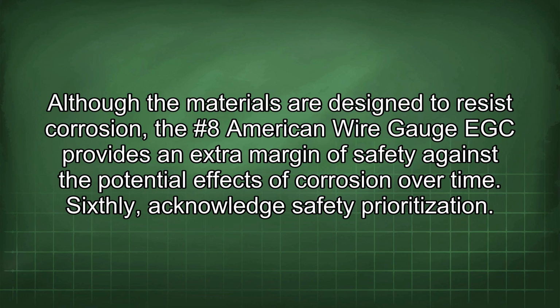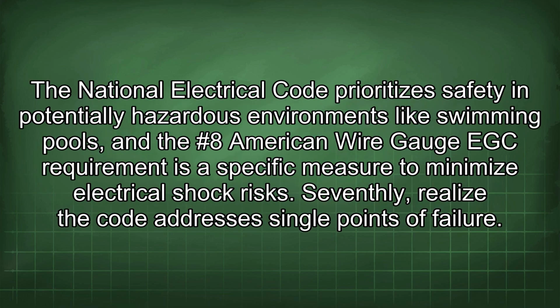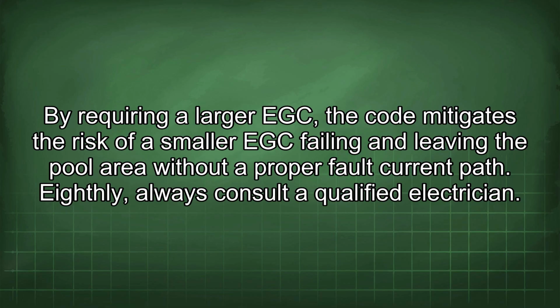Sixthly, acknowledge safety prioritization. The National Electrical Code prioritizes safety in potentially hazardous environments like swimming pools, and the #8 American wire gauge EGC requirement is a specific measure to minimize electrical shock risks. Seventhly, realize the code addresses single points of failure. By requiring a larger EGC, the code mitigates the risk of a smaller EGC failing and leaving the pool area without a proper fault current path.